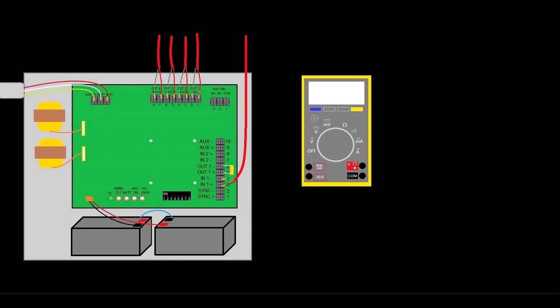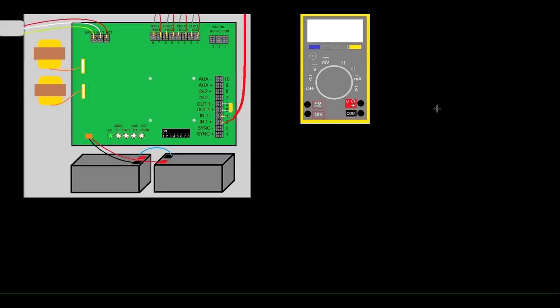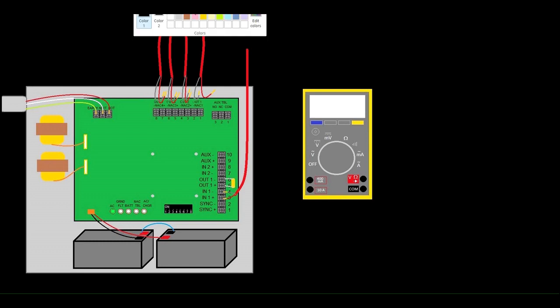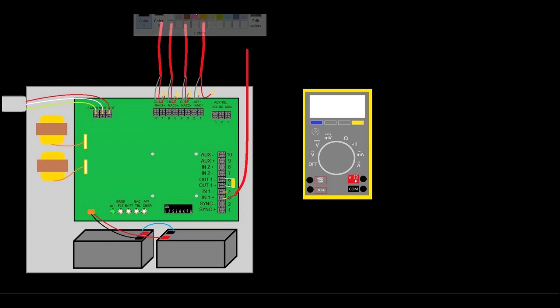So what you'll do is you'll disconnect them one at a time until that light goes out. I know I just said we were going to disconnect these circuits one at a time, but I decided it was easier to draw them just disconnected all at once. If you were to remove these one at a time and wait for your ground fault light to go off that's fine, but if you are able to read the meter and you trust yourself reading a meter, then there's no harm in disconnecting them all, seeing the ground fault light go out, and then just start taking meter readings. It's kind of six of one, half a dozen of another.